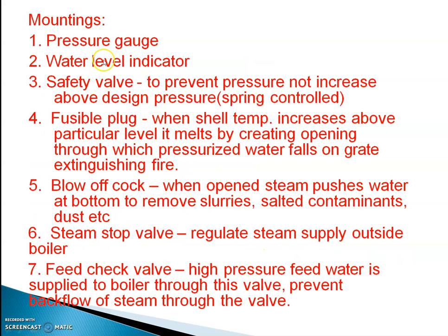Before operating the boiler, the mountings and accessories are very important. Pressure gauges maintain the pressure level with the help of Bourdon tube pressure gauges. The water level indicator is made of glass and is transparent, so we can see the water level in the boiler. Safety valves prevent the pressure from increasing too high, otherwise the boiler will burst.